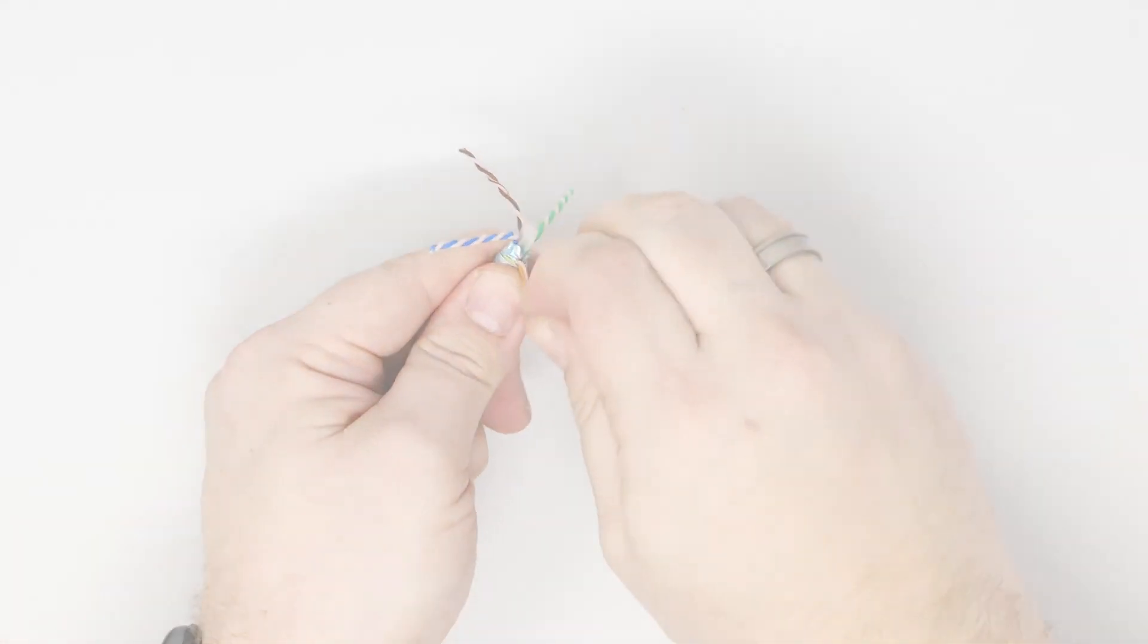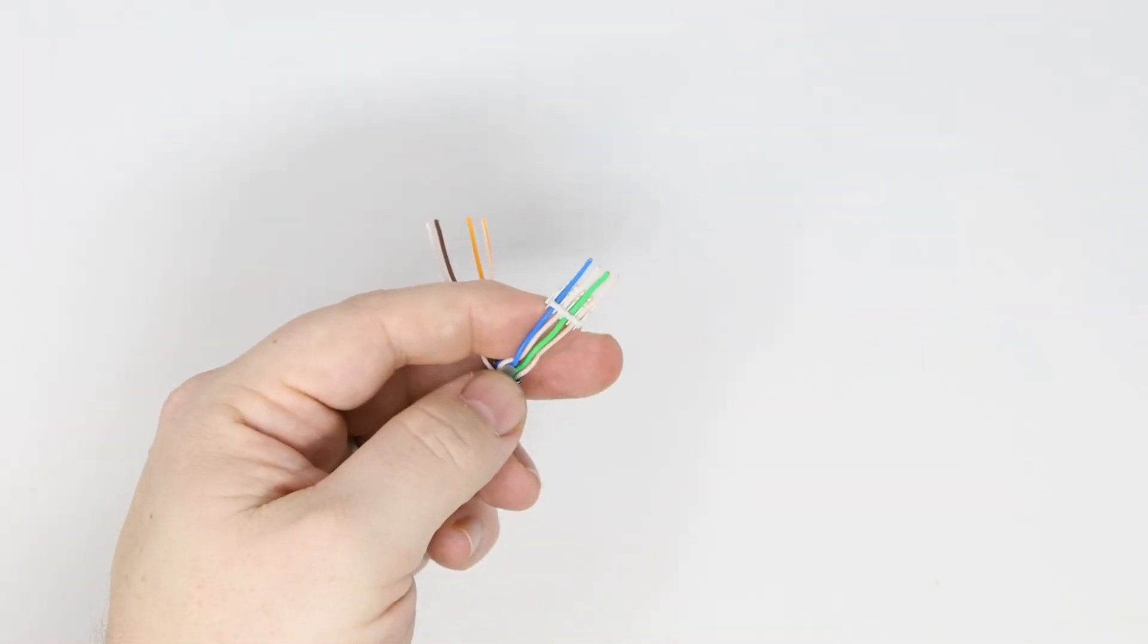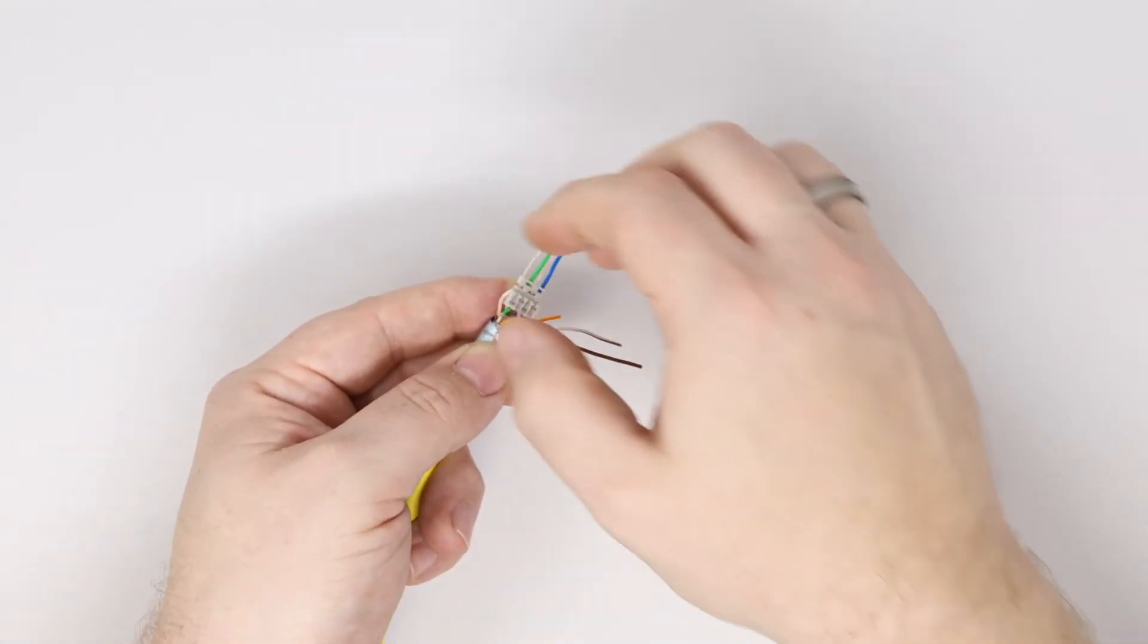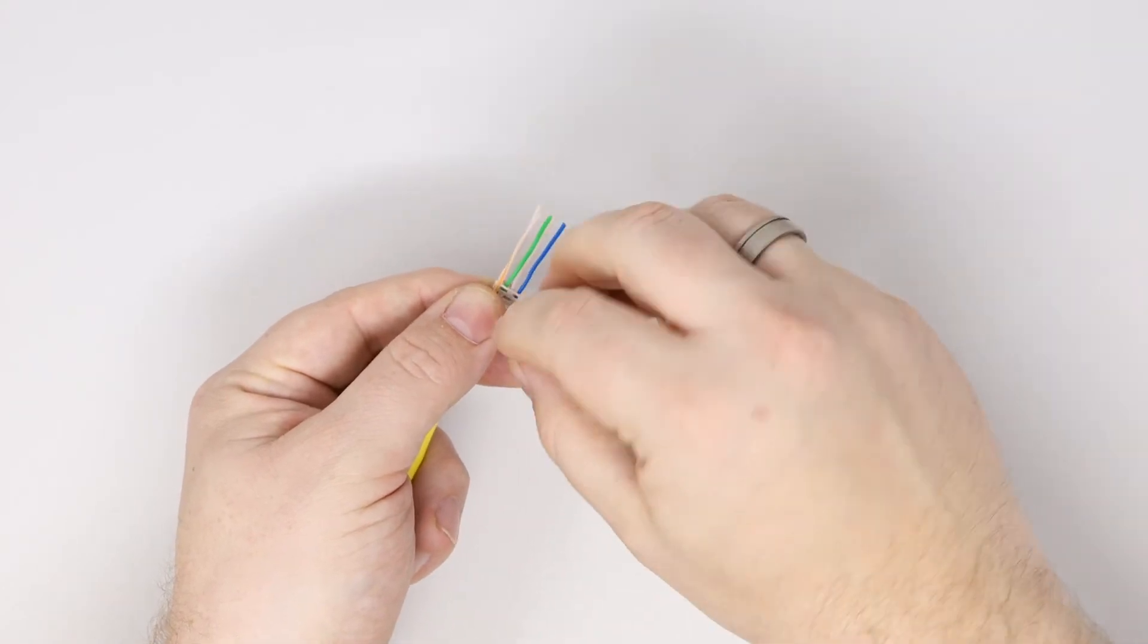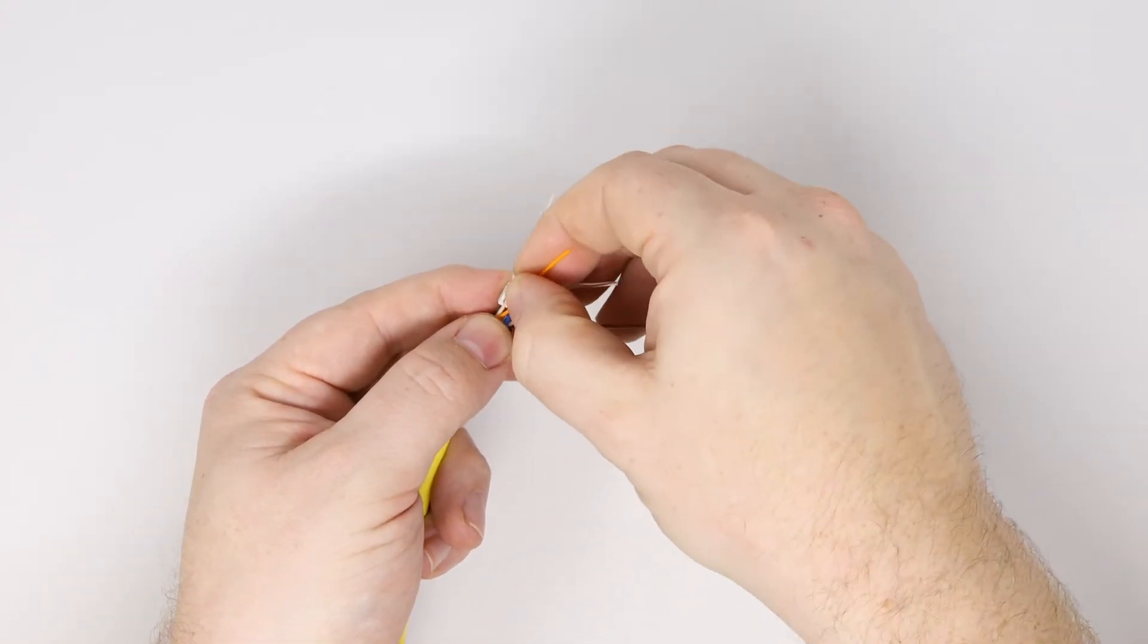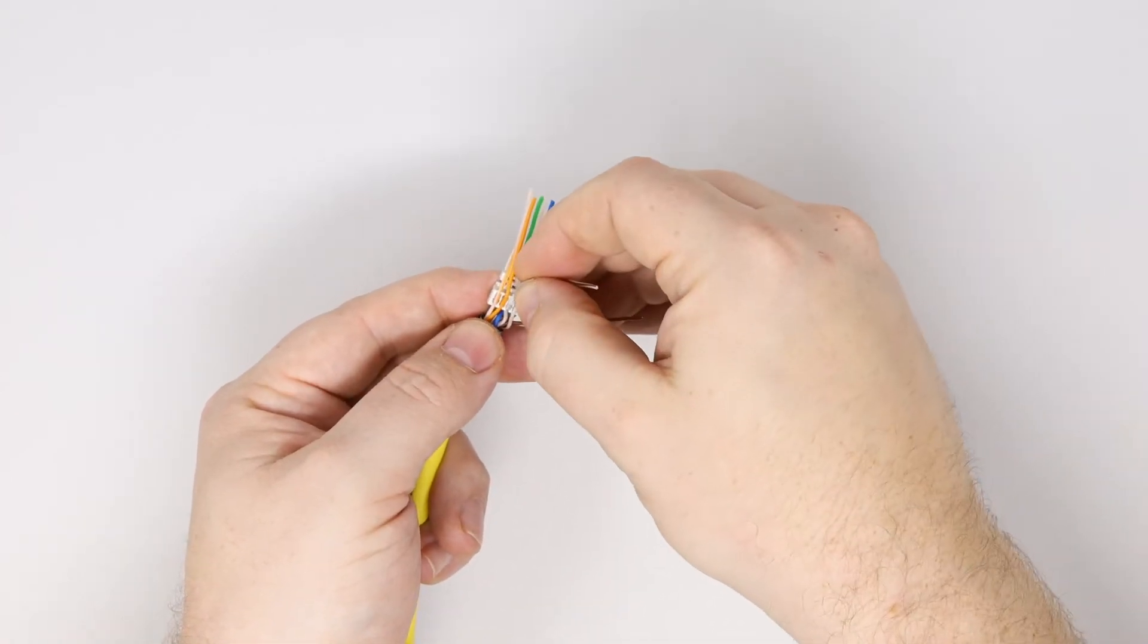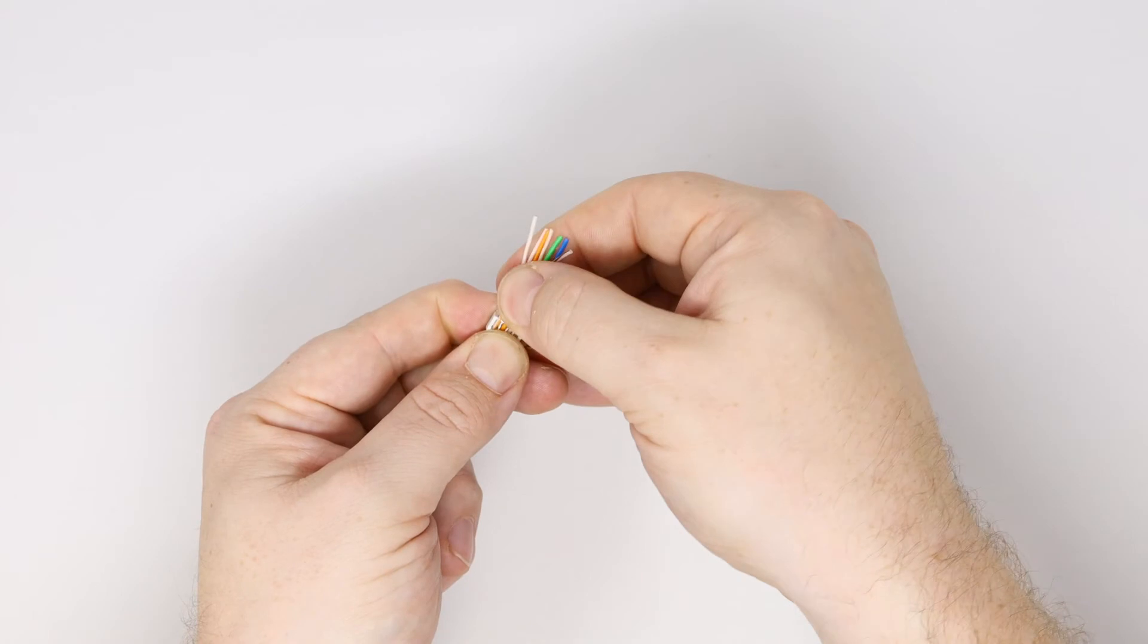Position the blue-blue white and the green-green white pairs together, and then the brown-brown white and the orange-orange white together, as this will ease their correct placement within the wire manager to the 568B wiring convention. The wire manager is clearly color coded to make this action easy and further ensure that the pairs are inserted in their correct wiring configuration position.